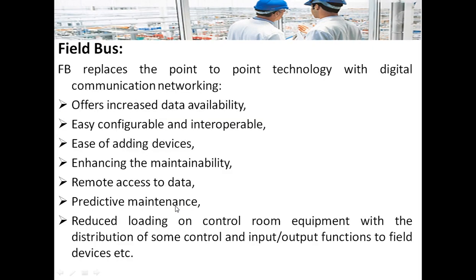These are the advantages of fieldbus over a conventional 4 to 20 milliampere point-to-point interface. Fieldbus devices offer increased data availability, are easily configurable, and are interoperable — meaning devices from different manufacturers are compatible with each other. The fieldbus supporting network makes it easy to add new devices and also enhances the maintainability of the system. Remote access to data, remote maintenance, and it also reduces the load on control room equipment through the distribution of control to field devices. For example, in Foundation Fieldbus, the PID block can be incorporated in field sensors or actuators, reducing the load on the control system.